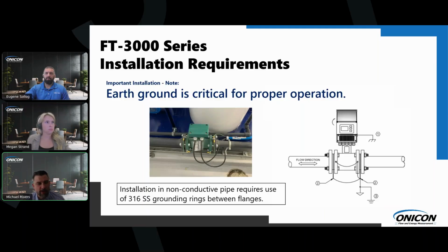There's more grounding that's required with non-conductive pipe, and that's because the pipe wall or the actual pipe acts as more of an insulator to any electrical noise, where in a metallic pipe we find the piping is used almost like an earth ground for that electrical noise. So with a non-conductive pipe, we require a little bit more hardware, grounding rings or grounding probes, more commonly grounding rings for an inline mag meter, where you're flanging rings in between the non-metallic flanges, and now you're grounding those rings to an earth ground. And what that allows is any of that electrical noise in the pipe to find a way to ground through those grounding rings so you're neutral at the point of measurement.